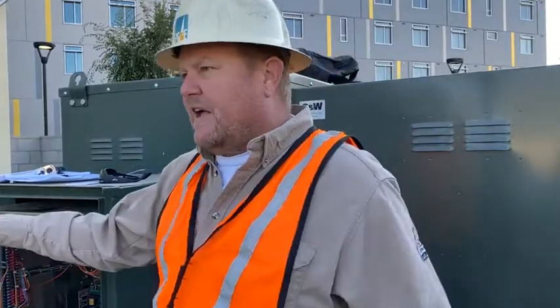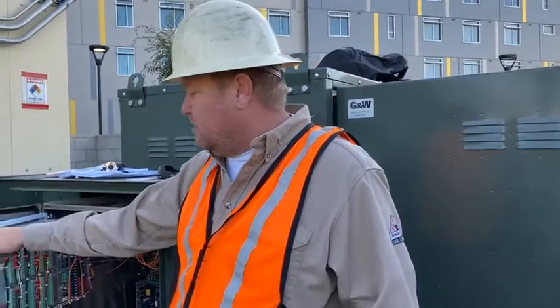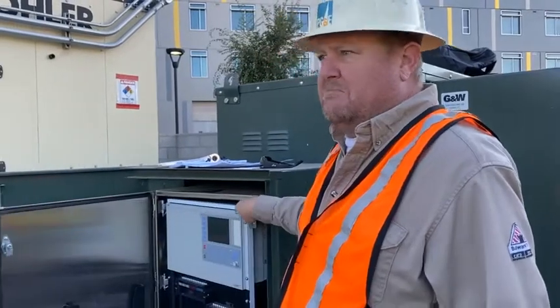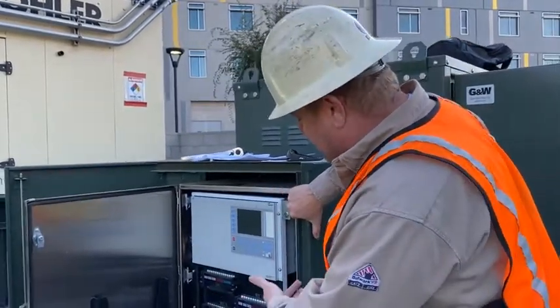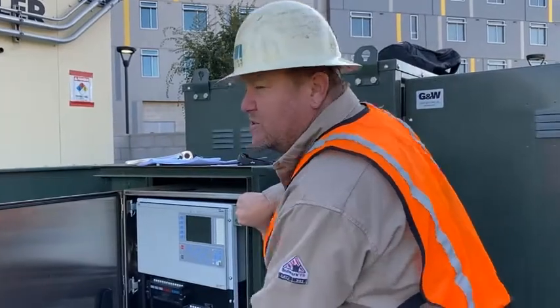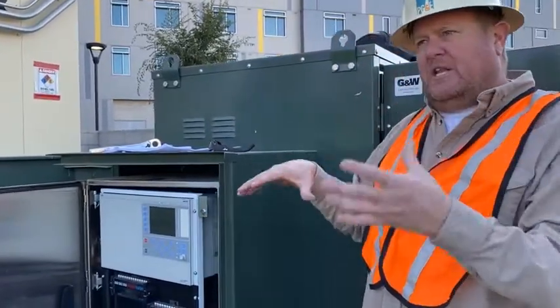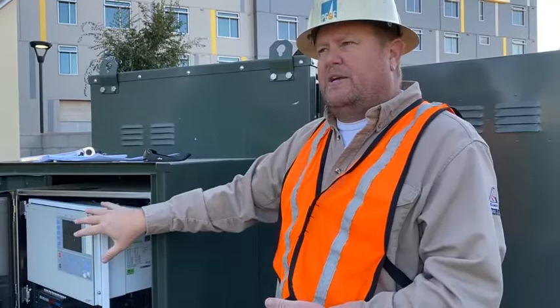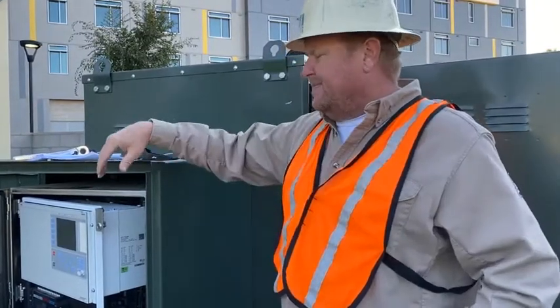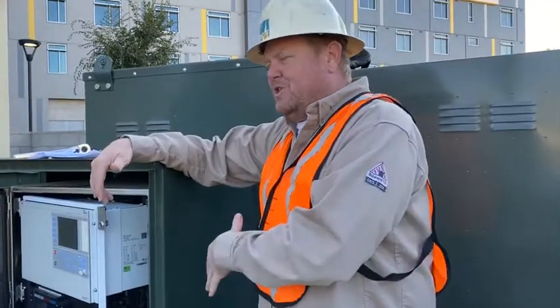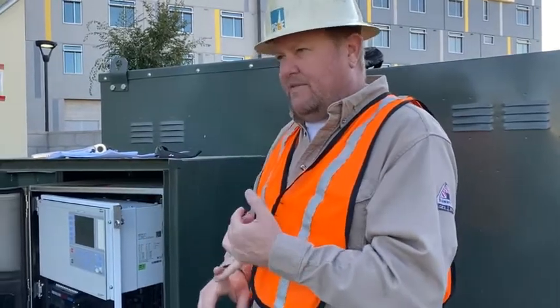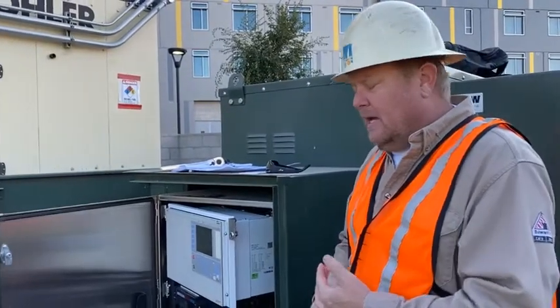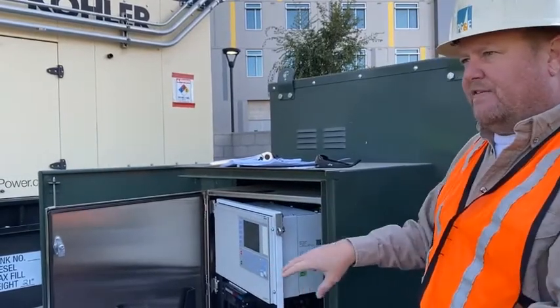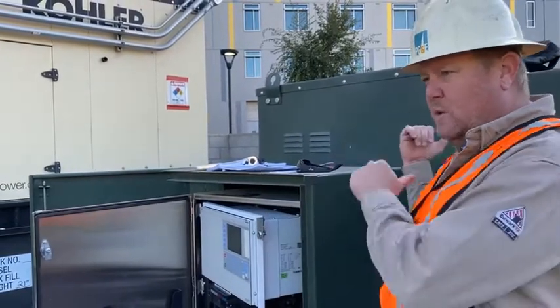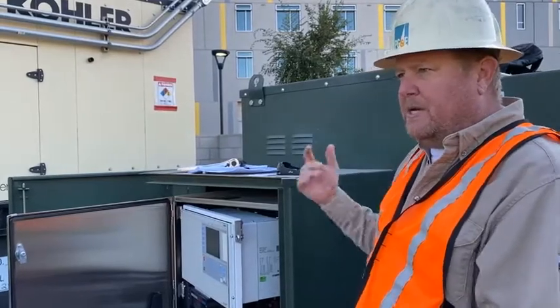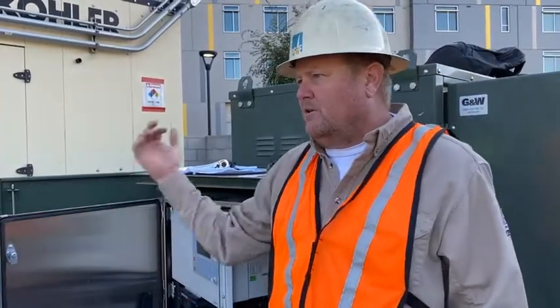Hampton Tedder does have guys that go out and test these relays. They'll come out on an annual basis, and that's why we have these test switches in here, so they can simulate and verify the relay is working properly. Usually when we start one of these up, the contractor will have a third-party testing company come out, run through and verify, do current injection, and make sure the switch is operating properly, tripping open, just like they would on a switchboard or your main switchgear.